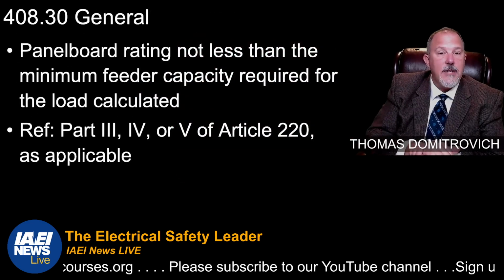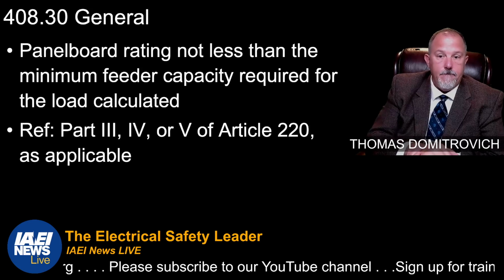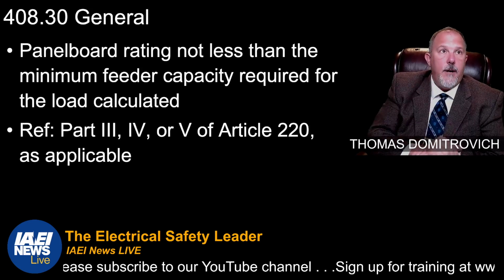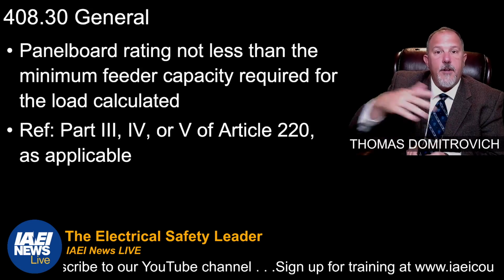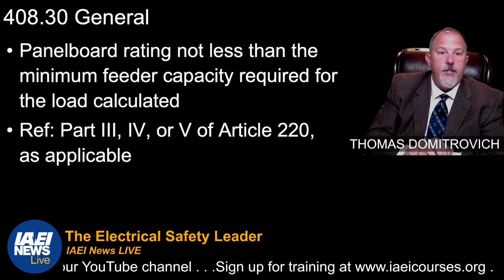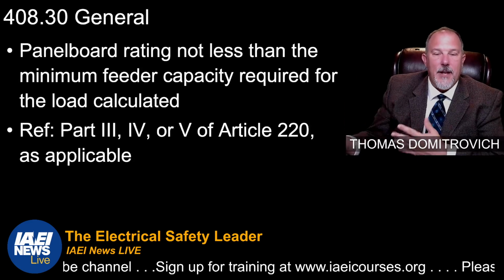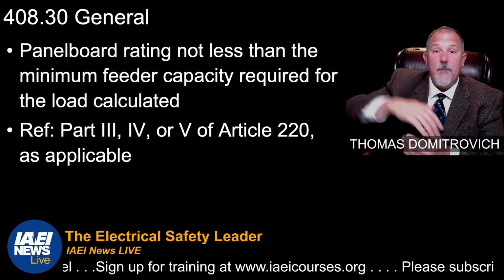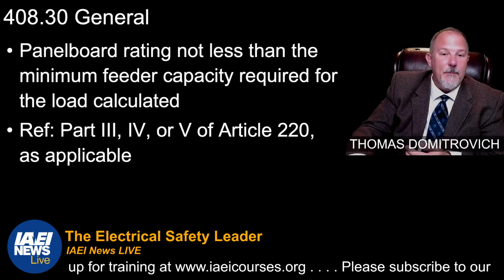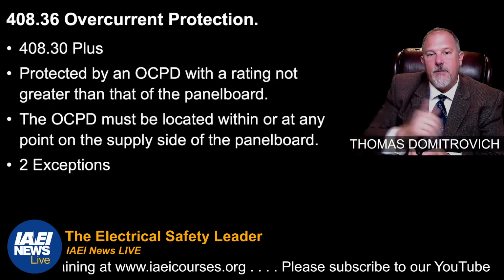Panel board ratings not less than the minimum feeder capacity. You calculate your load, and the panel board has to be able to supply the load. Obviously, it could be much greater, but it can't be less than the load. And they point you back to 220.